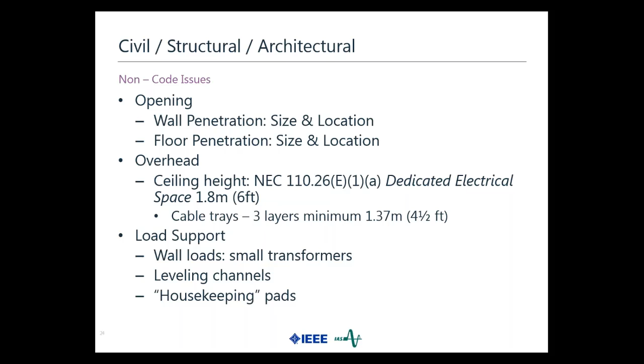We talked about the housekeeping pads in one of the pictures. And the other thing that you can get into is, does your switchgear require leveling channels? So you got to coordinate that. If you got a 5 kV gear, or 15 kV gear, you very well may have leveling channels under that gear.